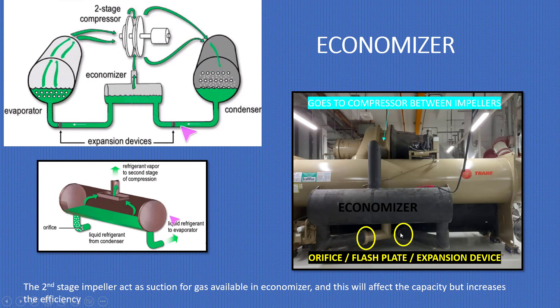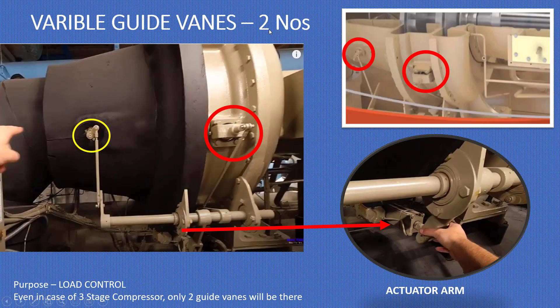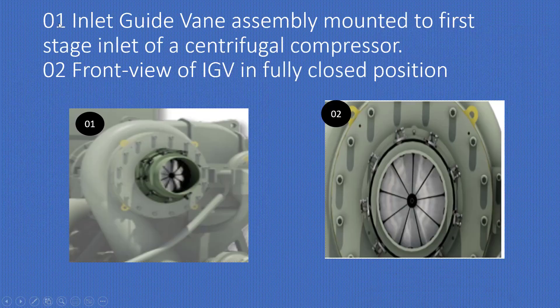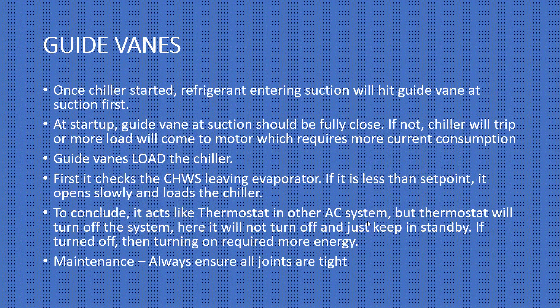You can see the economizer here with orifices on both sides — also called an expansion device. It goes to the compressor between the impellers. Variable inlet guide vanes (IGV), also called guide vanes, are available in two numbers to control the load. Even in a three-stage compressor, only two guide vanes are present: number one is the inlet guide vane assembly mounted to the first-stage inlet of the centrifugal compressor, and number two is the front view of the inlet guide vane in the fully closed position.